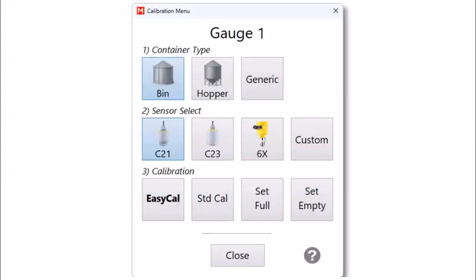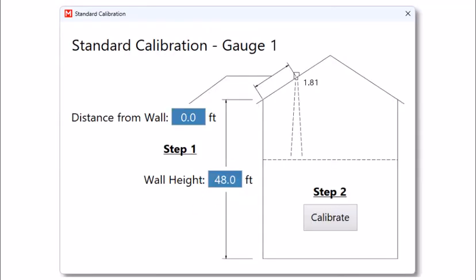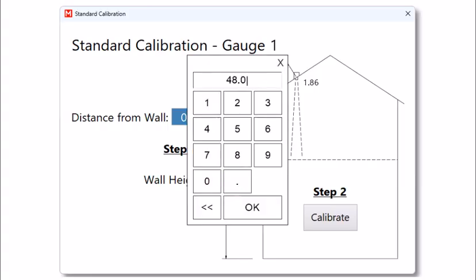The next option available for a standard bin is the standard calibration. It's still recommended that you place the sensor halfway up the roof, but it's not required. The standard calibration can be performed when the bin is not empty. Once again, we can see a live reading of the distance to the bin's floor or to the bin's contents. Enter the height of the bin's wall by selecting the bottom blue rectangle labeled Wall Height.